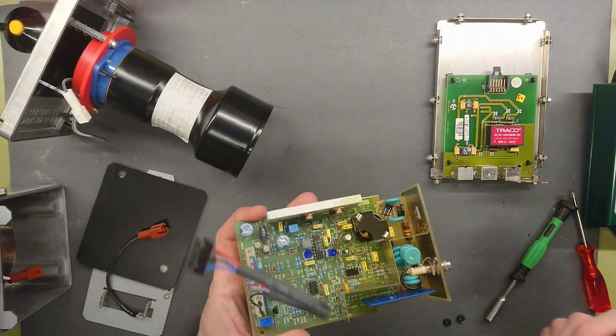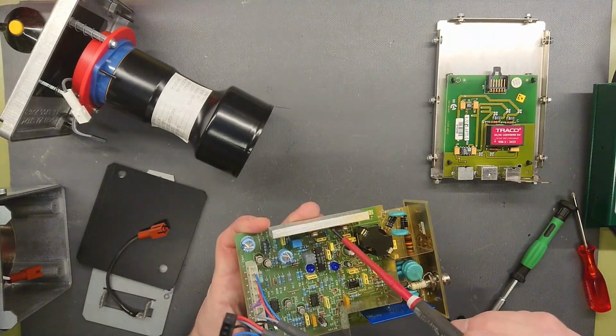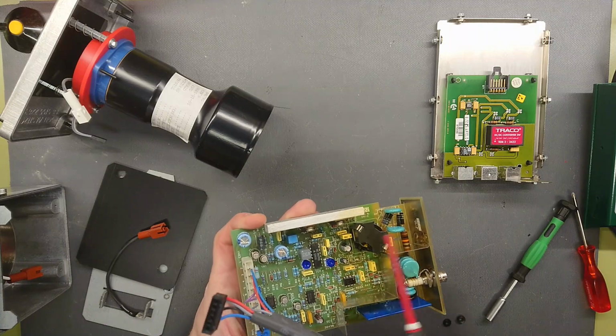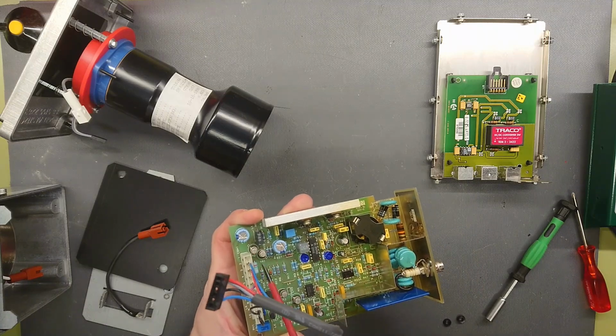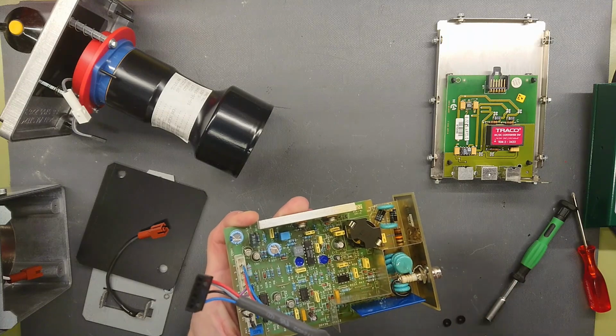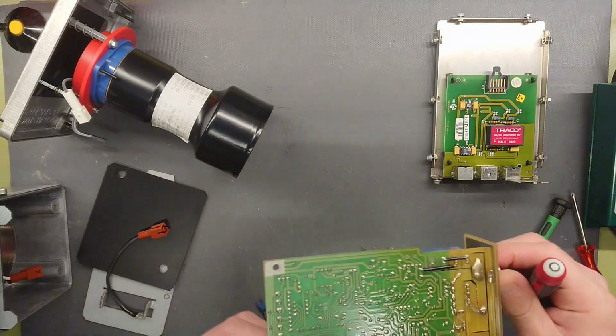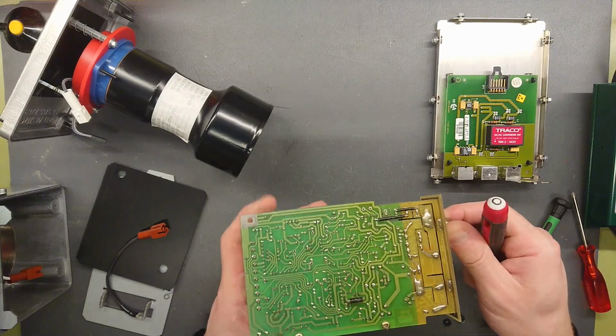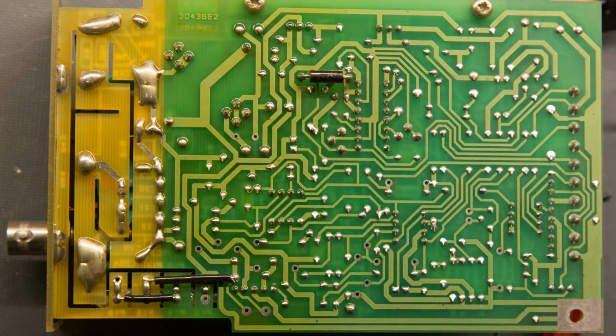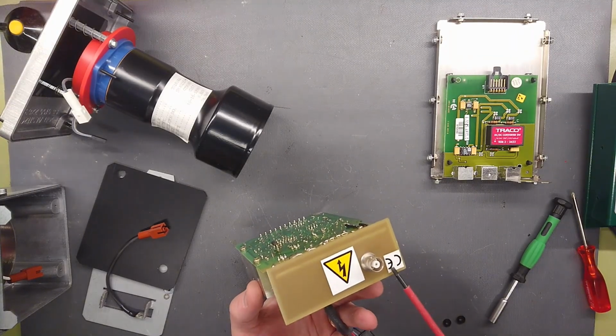We can also see a nice detail here that is conformally coated from around here and up, but not down here on this part. So it's only a coating in order to minimize corona. And you can see they really smeared on the soldering down here, and that is to avoid any kind of corona on the high voltage part, to make any pointy object as round as possible. And a small CE mark.